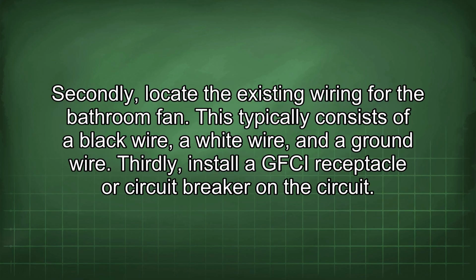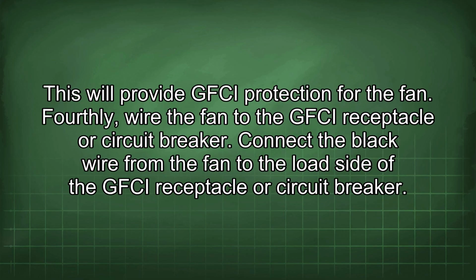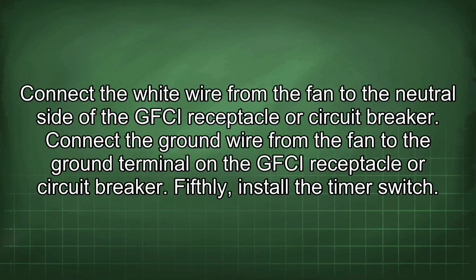Thirdly, install a GFCI receptacle or circuit breaker on the circuit. This will provide GFCI protection for the fan. Fourthly, wire the fan to the GFCI receptacle or circuit breaker. Connect the black wire from the fan to the load side of the GFCI receptacle or circuit breaker. Connect the white wire from the fan to the neutral side of the GFCI receptacle or circuit breaker. Connect the ground wire from the fan to the ground terminal on the GFCI receptacle or circuit breaker.